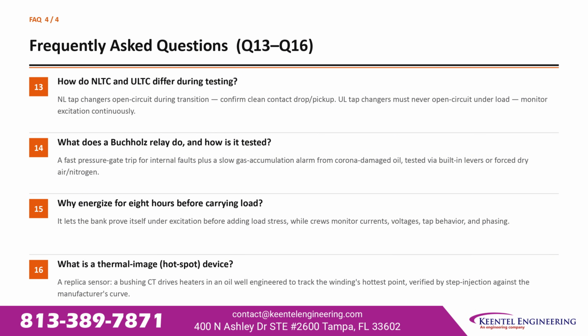Why energize for 8 hours before carrying load? It lets the bank prove itself under excitation before adding load stress, while crews monitor currents, voltages, tap behavior, and phasing. What is a thermal image or hotspot device? A replica sensor, a bushing CT, drives heaters in an oil well engineered to track the winding's hottest point, verified by step injection against the manufacturer's curve.